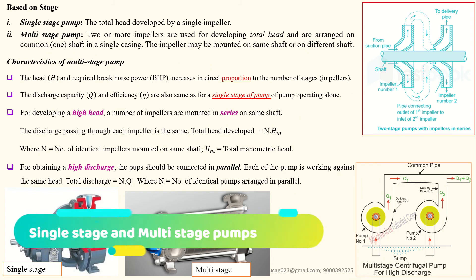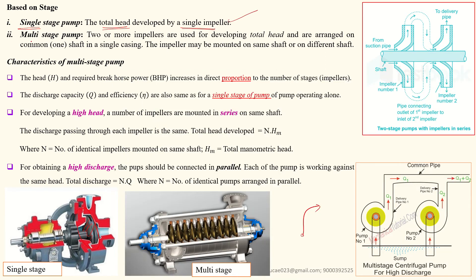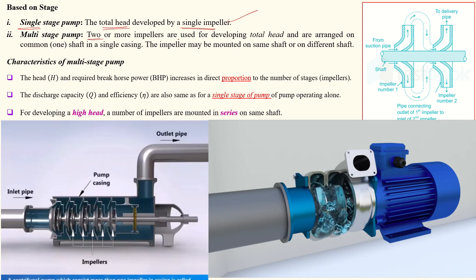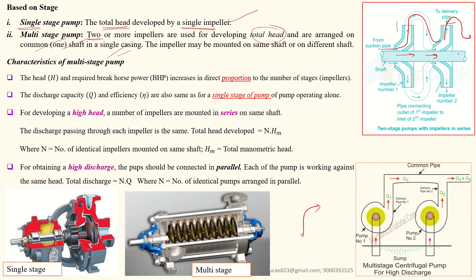The next classification is based on stages: single stage and multi-stage. In a single-stage pump, the total head is developed by a single impeller only — the pump has one impeller and can pump water up to a certain height. In a multi-stage pump, more than two impellers are used to develop the head. These impellers are arranged on a common single shaft. The first impeller pumps water to the next impeller, which pumps to the next, and so on.